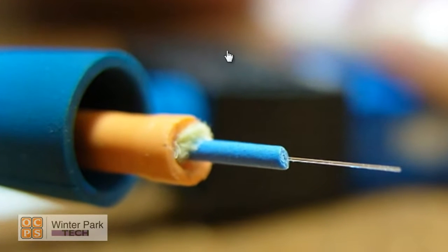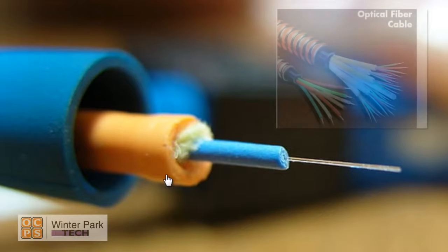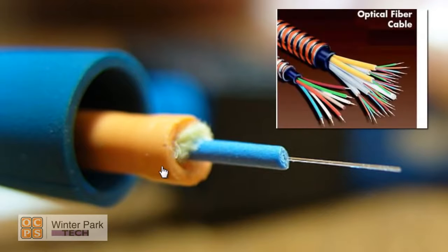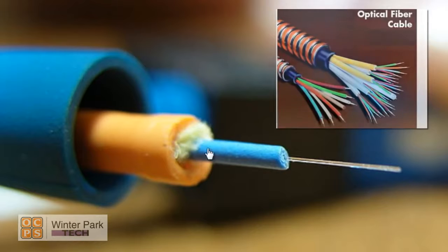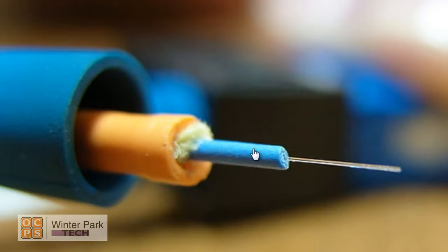Here's an example of multi-mode fiber. Notice the jacket is orange. That is typically multi-mode. If this jacket is yellow, that is in most cases single mode. Notice we have some cotton fibers here. Again, we have some jacketing, silicone, polyurethane, whatever. This right here is the cladding. This that you see visibly with your eyes is cladding. Very, very small is a micron piece of glass that goes right down the center.